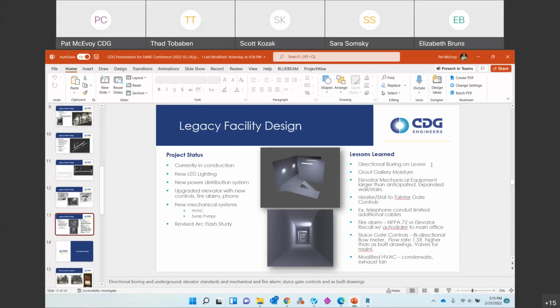One of the more interesting ones was the fire alarm system for the elevator. It was designed toward NFPA 72 rather than the elevator recall design with an auto dialer to the main office. The elevator recall system is actually a little more stringent than the NFPA 72 standard, so it required them to rework how they did the fire alarm system, mainly meaning the fire alarm system has to be intelligent enough that when it detects fire at a certain level, the elevator does not open its doors to that level, avoiding levels having a fire or smoke event. That was part of the big reason. Also, the auto dialer goes to the main office, not directly to the fire department, it calls the county. That's a little different thing we learned along the way.